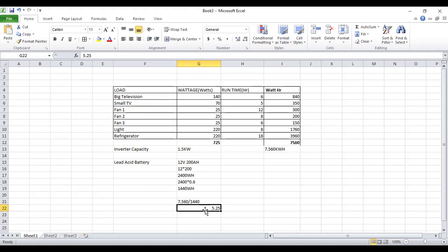Are you with me? But I still don't like the idea, because once the voltage goes low, it means you have to handle a lot of current to get the desired power. I don't like the idea of an inverter with a high capacity coming with a lower voltage, because you have to be handling a lot of current on the battery side of it. It's better to have a higher voltage, then the current reduces, so that you'll be handling less current on the battery part of it.